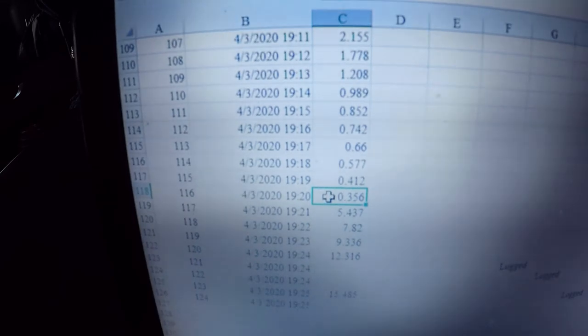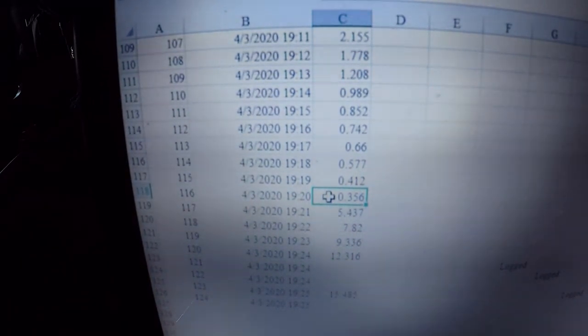Okay, so once again, there's my master temperature that we got off of our NIST thermometer. These are the ones I just wrote down from our logger. So I'm going to subtract these two and put the absolute value. It doesn't matter whether it's higher or lower. So it's going to be 0.4, 0.3, 0.3, 0.1, 0.1, and 0.1.